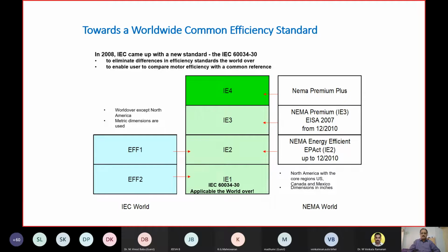While IEC was using the loss subtraction method for measurement of efficiency of motors, NEMA was using a direct efficiency estimation or efficiency calculation by measuring both the input as well as the output power. Output of a motor, as you all know, is the torque. So you need a torque to measure accurately the output power and then convert that into kilowatts, so that you are able to compare the output divided by input and arrive at the efficiency. Whereas in the case of IEC, we were taking the input power, subtracting the losses, and arriving at the output power as input minus losses. So therefore, efficiency used to be still output by input.